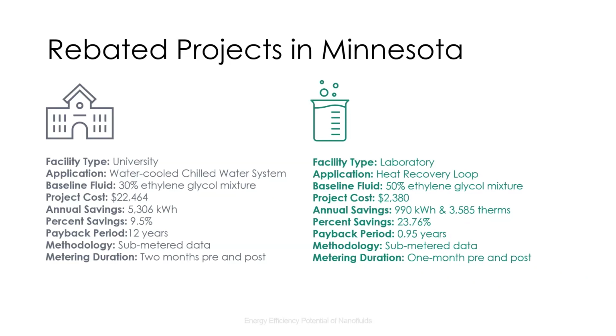As you can see, the chiller measure had a longer payback at about 12 years compared to the heat recovery loop, which was about less than a year. Those differences stem from a couple different factors. The first was that the loop volume and the cost required to fill the system was much smaller in the heat recovery case than the chiller. Additionally, the savings benefit was able to be realized in the heat recovery loop throughout the year, whereas chillers only operate during the summer.